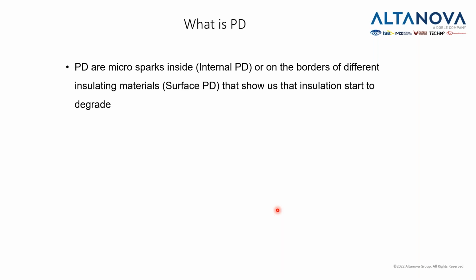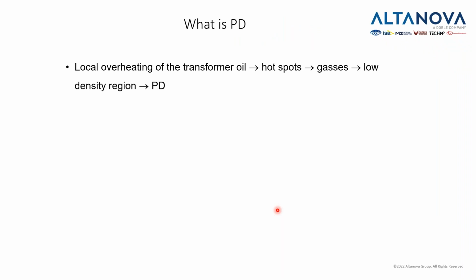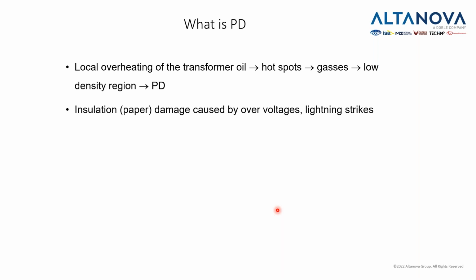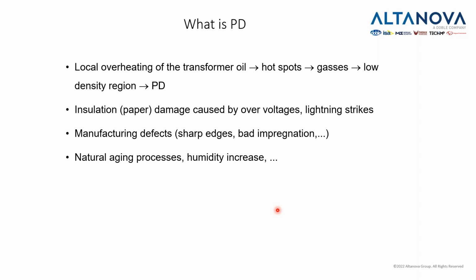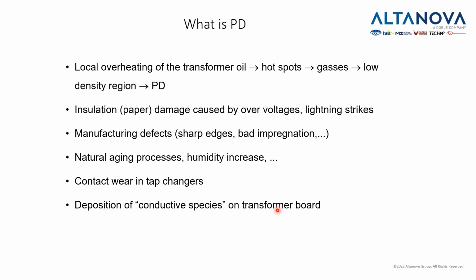And in general, you don't want to have any kind of sparks in your insulation. But when you start to have them, you want to understand that you have them and you want to move on with that, to see how strong it is, how repetitive is it, to understand what problems do you have. So it can show you if you have some local overheating in the transformer, if you have paper damage caused by overvoltages or lightning strikes, manufacturing defects, or if some aging processes on the insulation has taken place, or you have contact wear in tap changers, or deposition of conductive species on the transformer board, or faulty bushing taps. All that can be seen with the PD test.